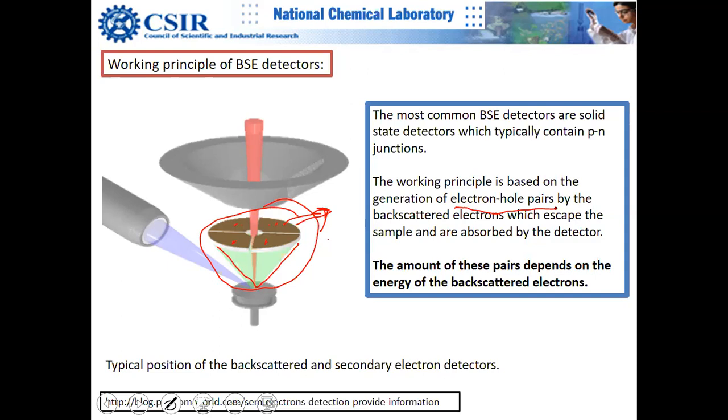We have already discussed that backscatter electrons are much higher in energy, so they generally do not get deflected towards the secondary electron detector, the Everhart-Thornley detector, which is at one side. It is placed off to the side purposefully so that you can deflect the less determined ones, the secondary electrons, which do not have much energy.